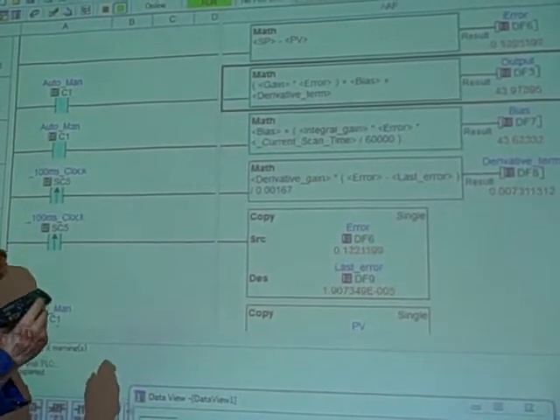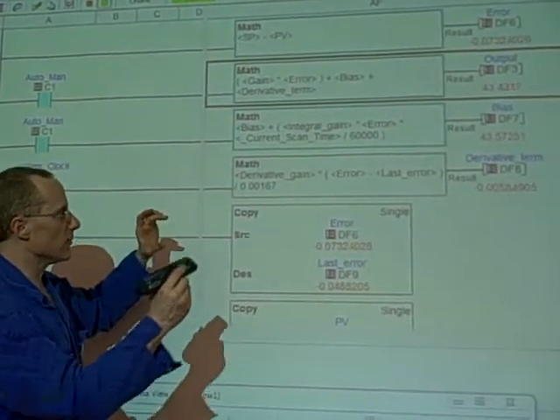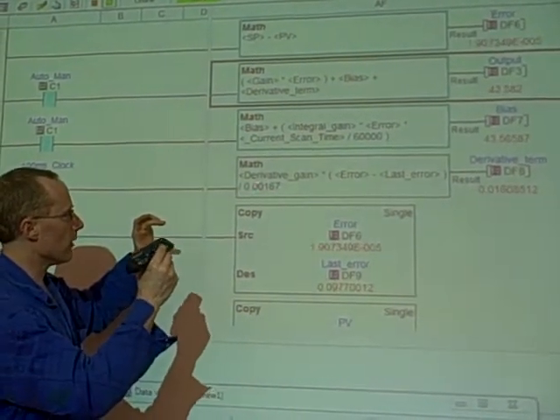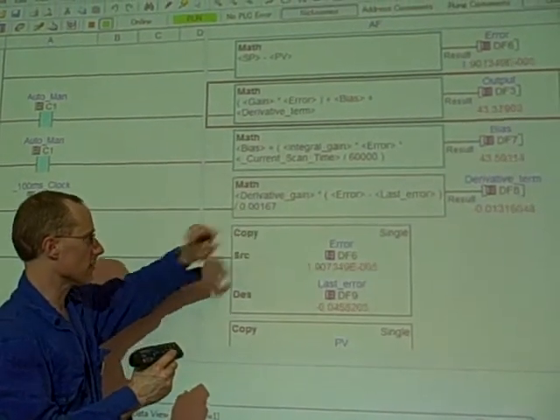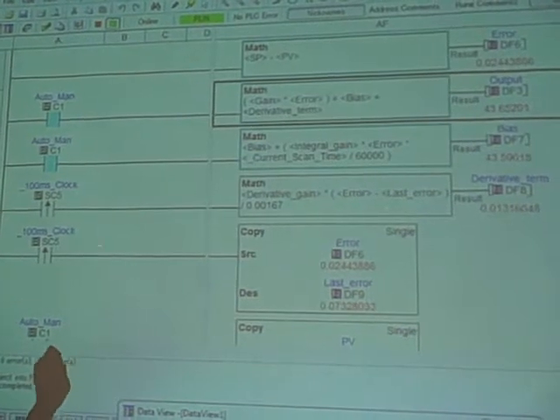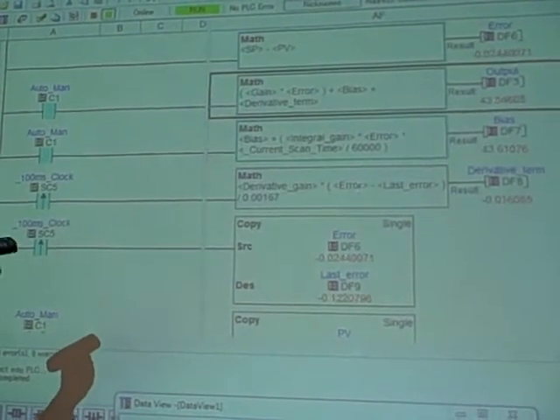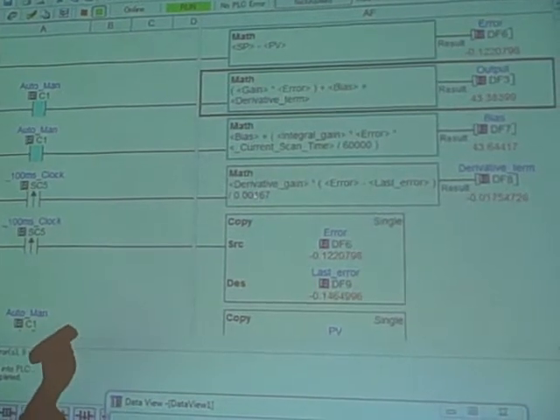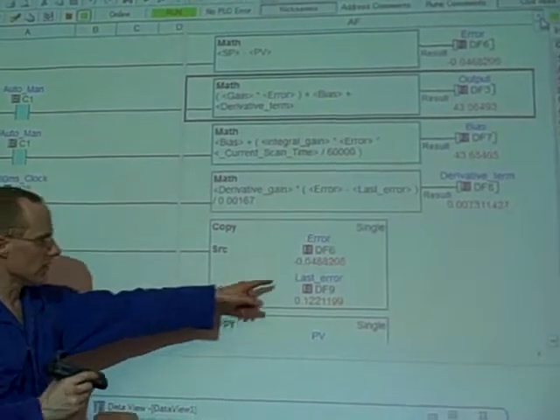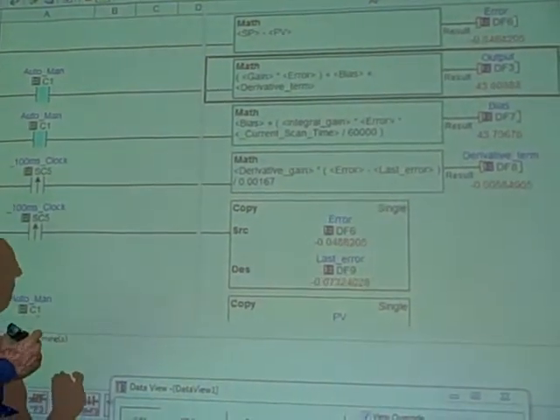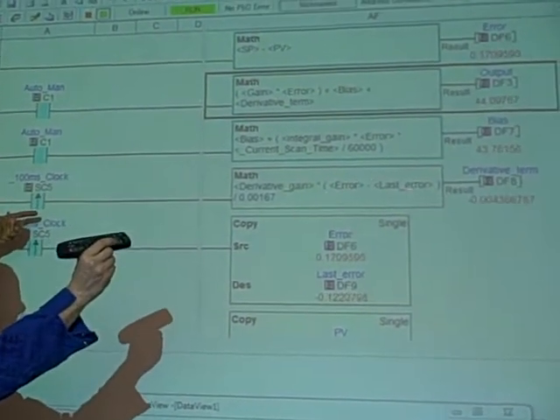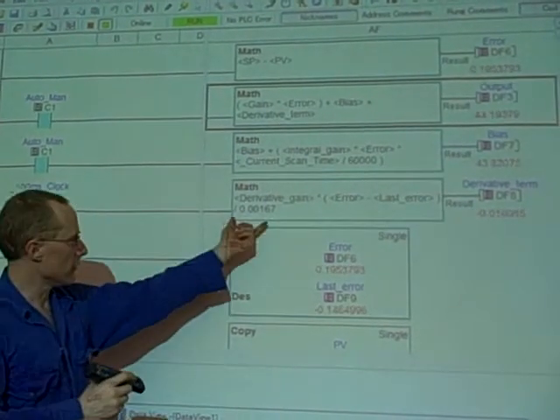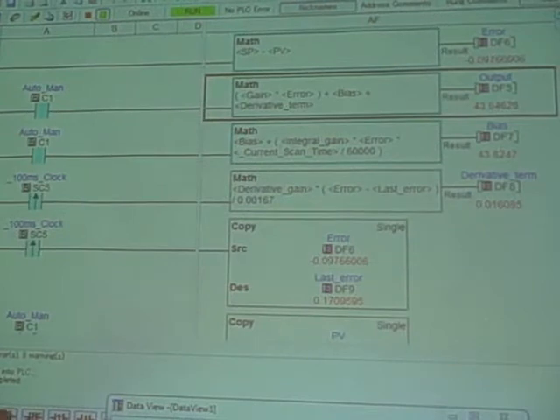So we've turned the derivative scan time down to basically ten times a second. So every tenth of a second, it recalculates rise over run. Rise being the error minus the last error, and the run being one tenth of a second expressed in units of minutes. Then over here is where we update our last error term. After it calculates rise over run, the error minus the last error divided by the run in time, it updates the last error variable with the present error. And then it waits another tenth of a second, does it again, checks the present error minus the last error, that's our rise, divided by our run in time, updates the last error, and waits another tenth of a second.